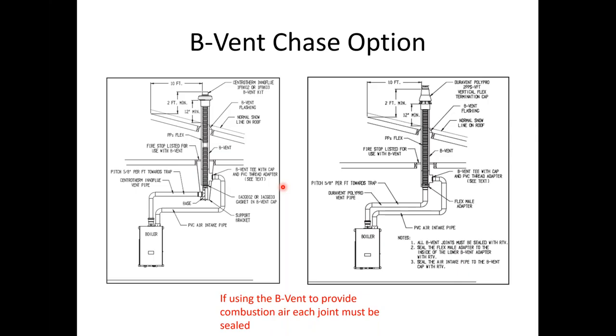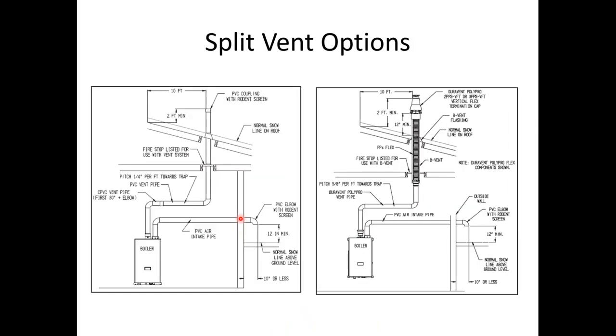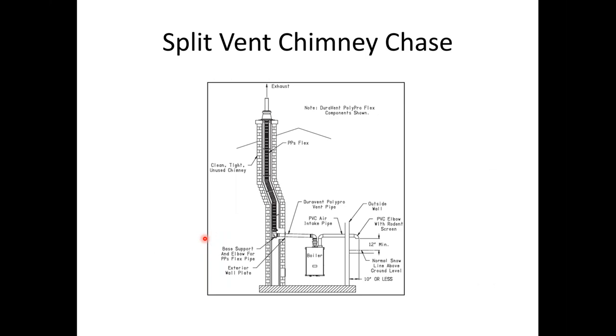We do have a B-vent chase option, where you can use the B-vent for your fresh air intake if you can get to every joint in the B-vent chimney and seal it. My stance on this is if I can get to every joint in the B-vent chimney and seal it, we wouldn't be using the B-vent chimney as a chase. But the option's there. And this is from the vent manufacturer itself that wants each joint sealed. Split options, we can go up through the roof with our exhaust and in through the sidewall with our air intake. And same thing with the chimney. Like I said, we had the chimney chase option, both flexible polypropylene, and there is a stainless steel option.